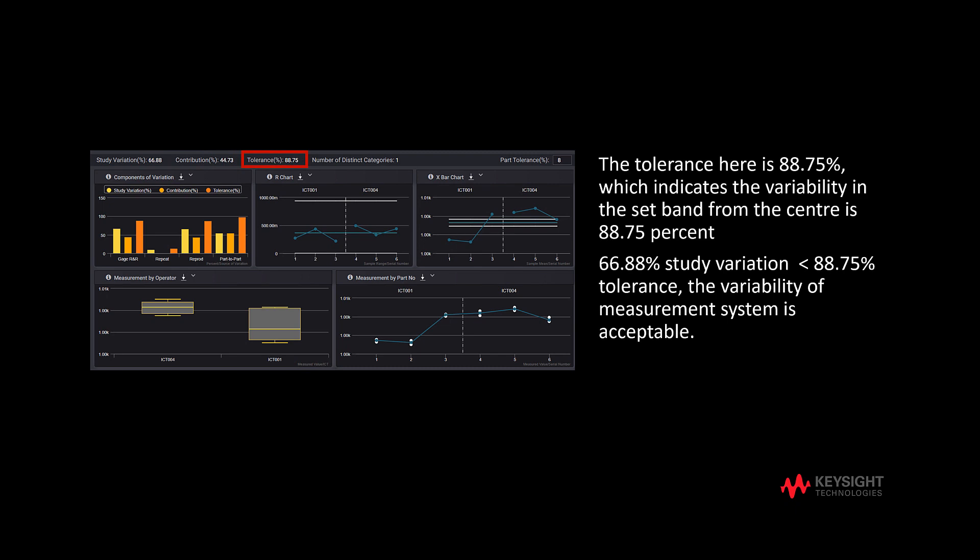The third metric is tolerance, which shows how much variability is in the set band from the center. Notice that the measurement system variability can be regarded as consistent if the value of study variation falls within the set tolerance band. In this case, the tolerance is 88.75% and the study variation is 66.88%.